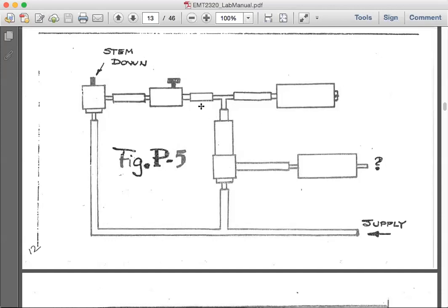Okay, and when you pressurize, of course, at the same time, you pressurize the air tank and the actuator. So let's say an actuator needs 15 psi to activate, and also let's say the force of the spring pushing the stem up is about 15 psi. You need this part of the system to have a minimum of 15-20 psi to actually activate the stem in this three-way valve.